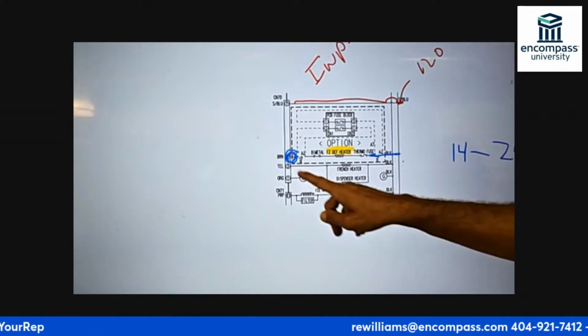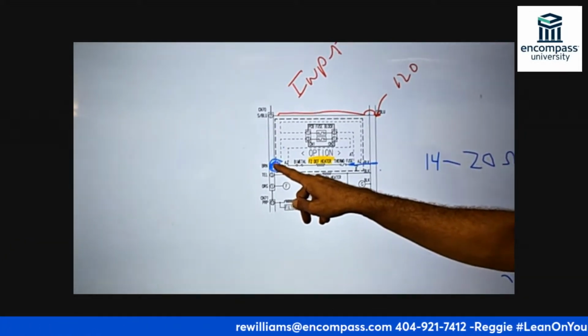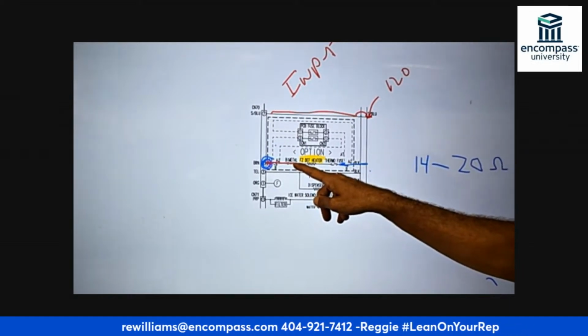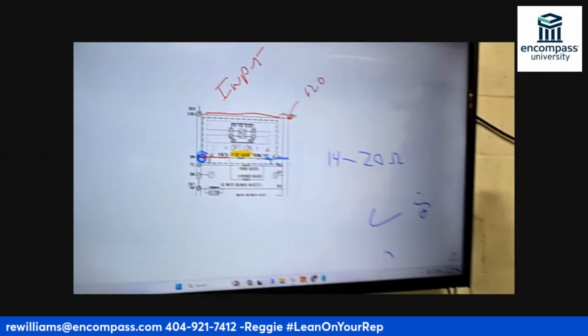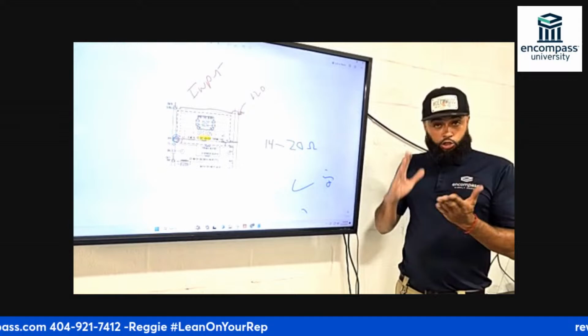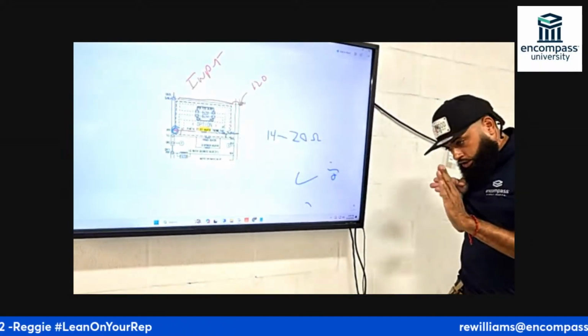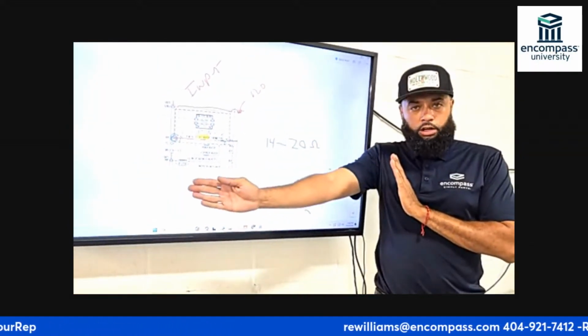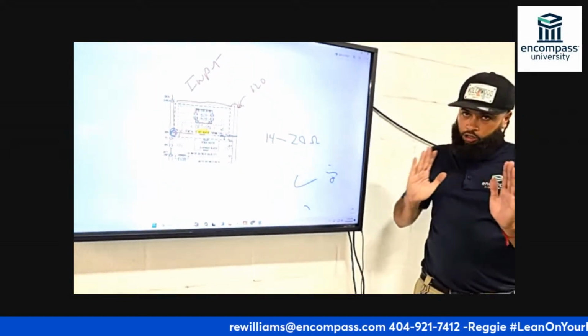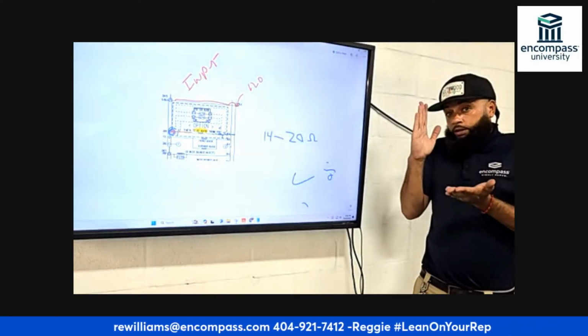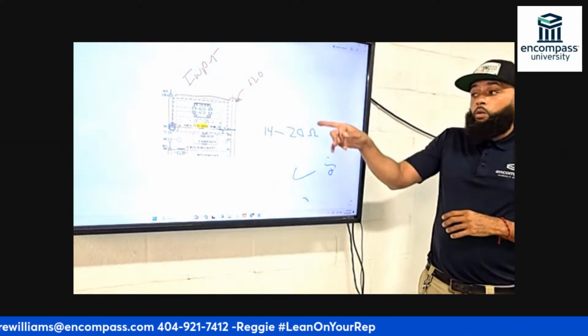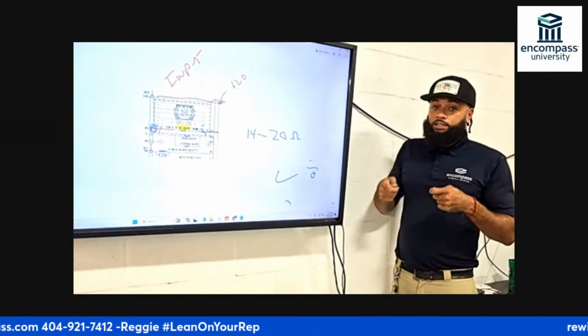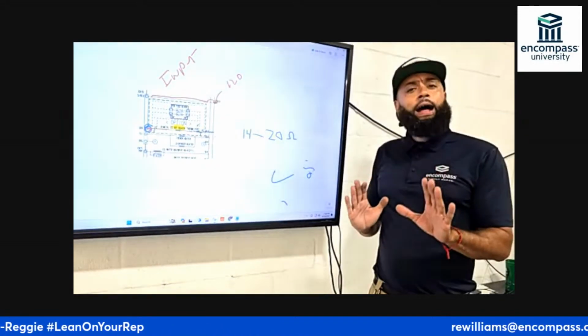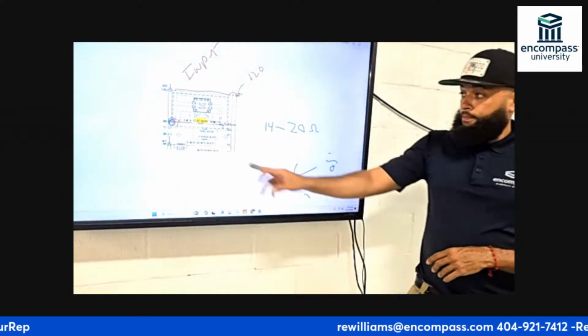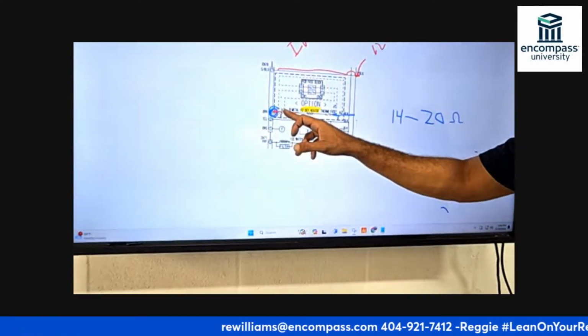Here's what happens: the board says, okay, you want it to go into defrost, I'm going to shoot it through this bimetal. If the bimetal is closed, meaning voltage or current can pass through it, that's a good thing. If it's open and frozen or cold, we may have a bad bimetal - we'd have to test it for continuity. But for now, let's just assume it's working, so voltage will pass through the bimetal.